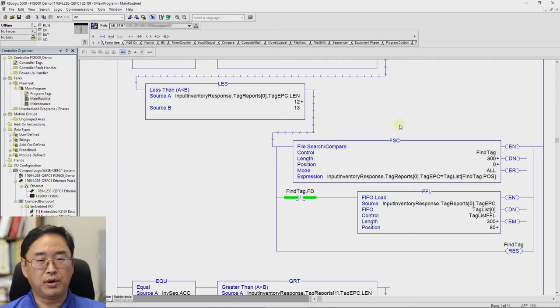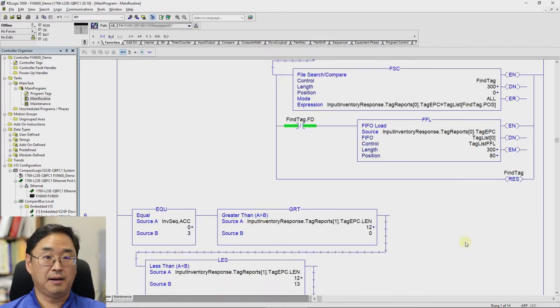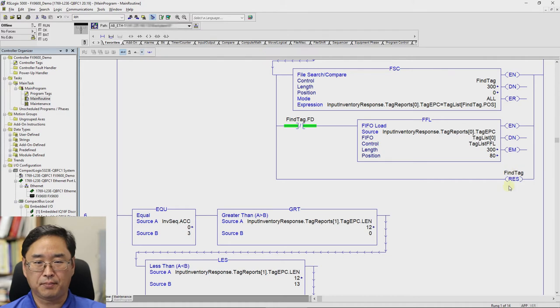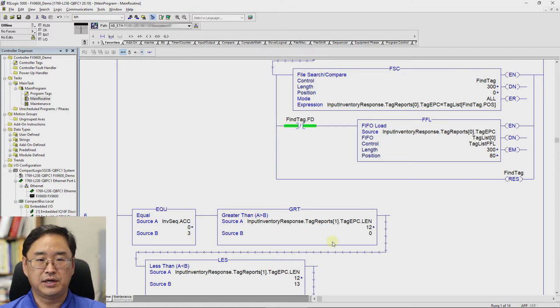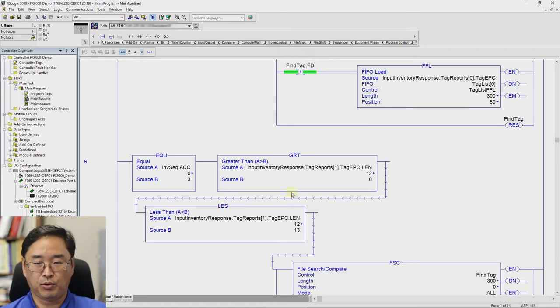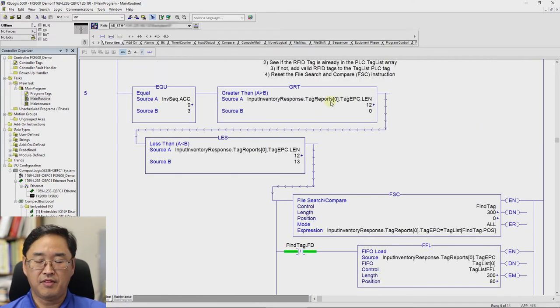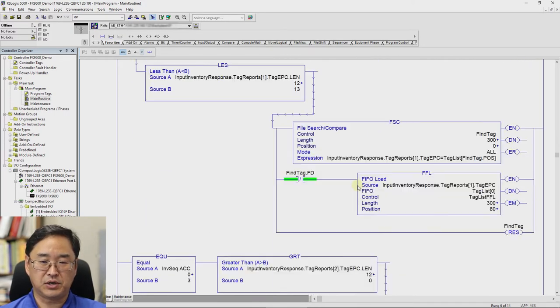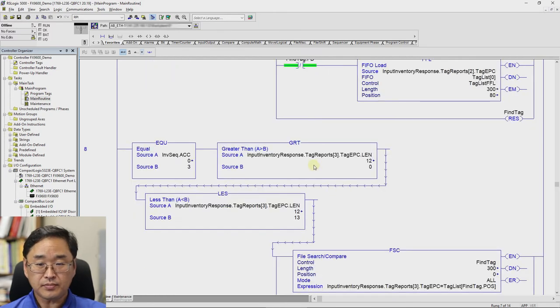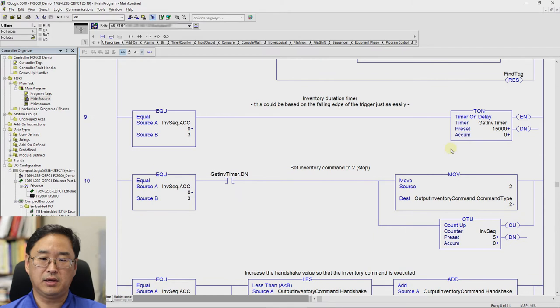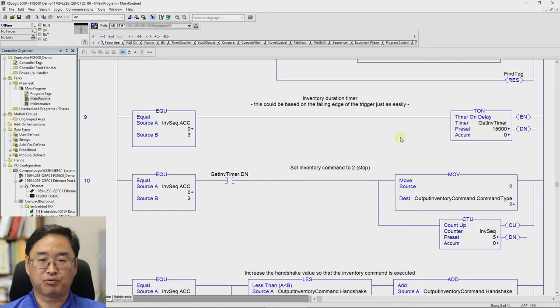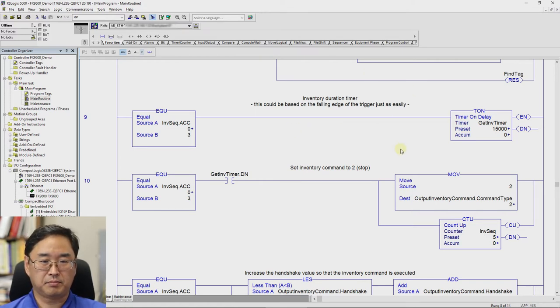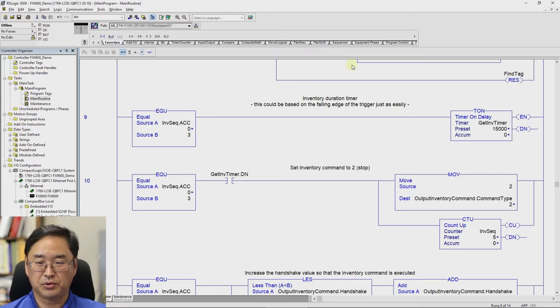At some point, you are going to have to figure out how you are going to end your process. I'm using a timer. You can use a second input. You can do the falling edge of the first input. However you choose to do this, you're going to need something that basically says, hey, at this point, set my inventory command to two, which is stop, and then increment the sequence so that I process my handshake again, which will then get me to a point where this command is executed, and it'll stop the read process. And then I do another increment and this is resetting everything.